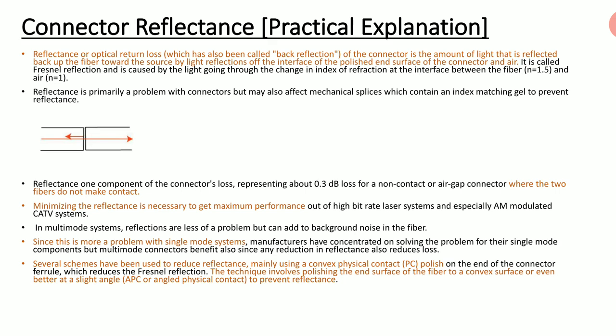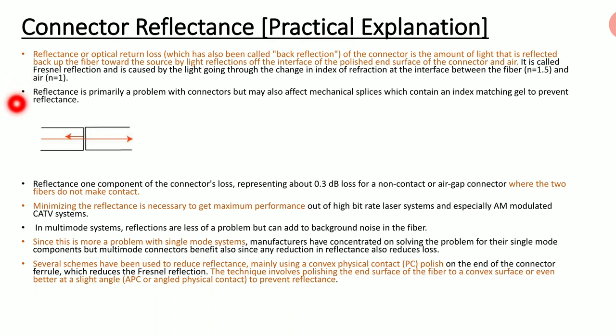Connector reflectance, also called optical return loss or back reflection, is the amount of light reflected back into the fiber toward the source by reflections at the interface of the polished end surface, the connector, and air. This is called Fresnel reflection, caused by light passing through the change in index from the refractive index of the fiber (1.5) to air (equal to 1). Reflectance is primarily a problem with connectors but may also affect mechanical splices, which use an index matching gel to prevent reflectance.